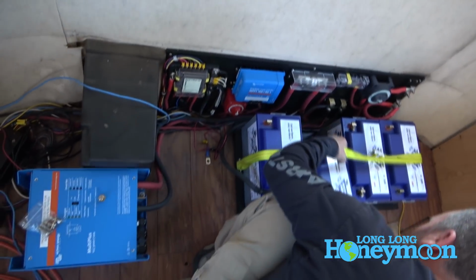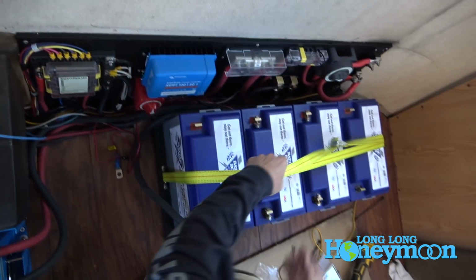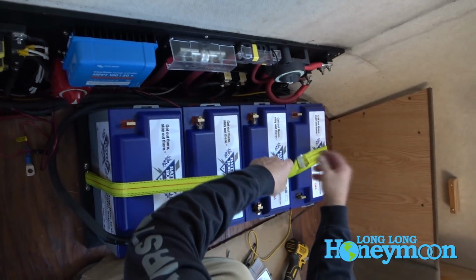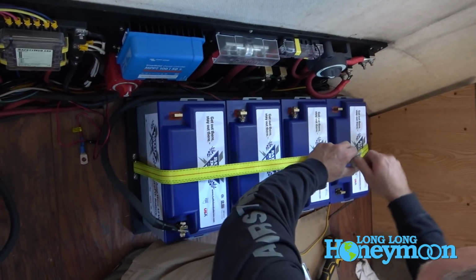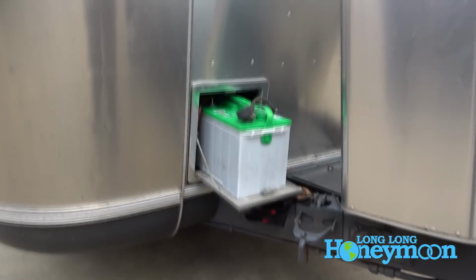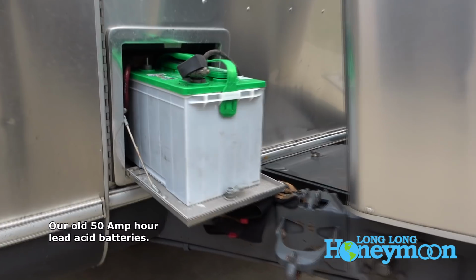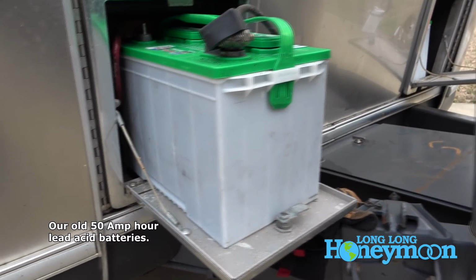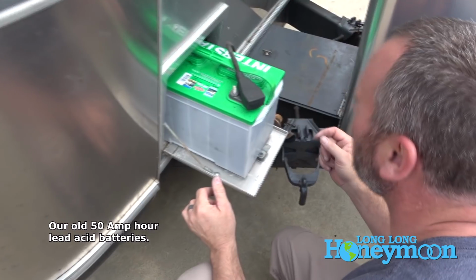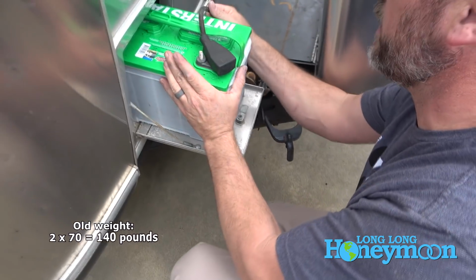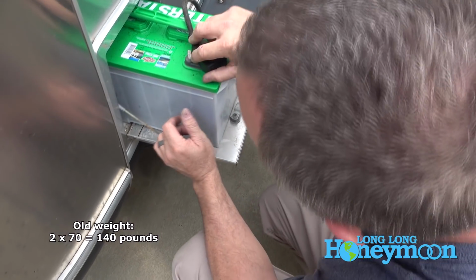Each one of these batteries only weighs 31 pounds. The old setup had 2 flooded lead acid batteries that weighed about 70 pounds apiece, and they were 100 amp hours each, but you could only use 50% of their capacity. So you had 200 amp hours of lead acid batteries and only 100 amp hours of usable energy.